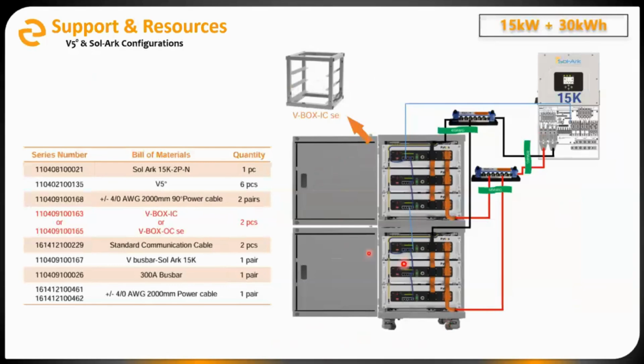These are screenshots from a configuration guide we've made for Sol-Ark systems. This shows some common battery and Sol-Ark pairings with the basic bill of materials to aid in ordering and system design. This one has 6 batteries specifically. We're using our flex bus bars, the VBox IC cabinet, stacking 2 of those on top of each other, and then a couple of bus bars to join the cabinets in parallel, and a single run of cables to the Sol-Ark 15K.